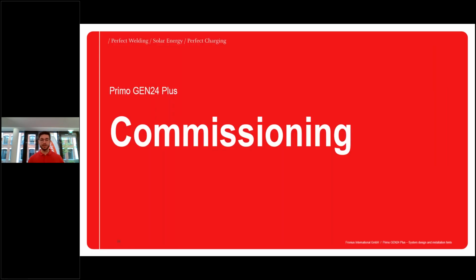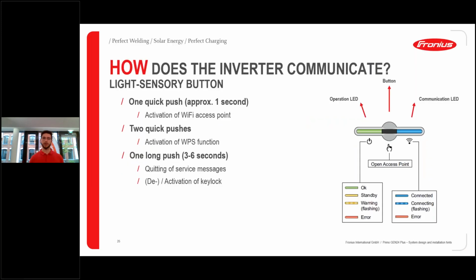Okay, last but not least, I want to take a closer look into the commissioning of the Primo GEN24 Plus. And before we talk about commissioning, of course, we need to talk about how the inverter actually communicates. We don't have a display like we have on the previous products, the SnapINverters, but we have status LEDs. We have 2 of them, and in the middle of those status LEDs, we have a light sensory button. And this is actually the way we communicate with the inverter. This is how we can see and respond to the inverter, and where we can open the access point, for example.